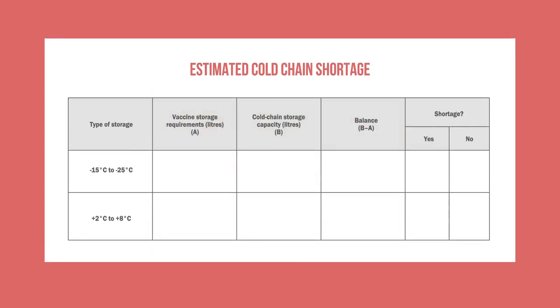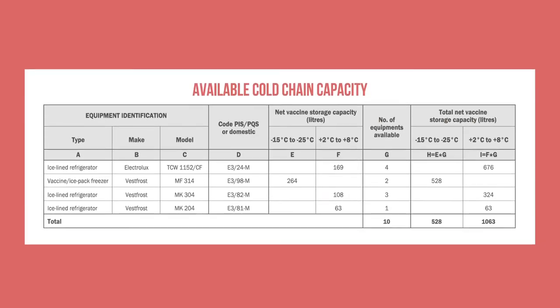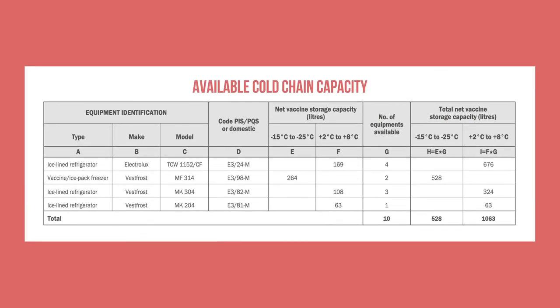For example, let us say you had 1,063 litres of refrigerator and cold room space available, but you need 1,200 litres for an incoming vaccine shipment. When you subtract 1,200 from 1,063, you get a negative number. That means you will need to find additional cold chain storage space to safely store all your vaccines. In this video, we looked at how to calculate cold chain storage capacity and determine if there is sufficient cold chain storage capacity for your vaccine requirements.